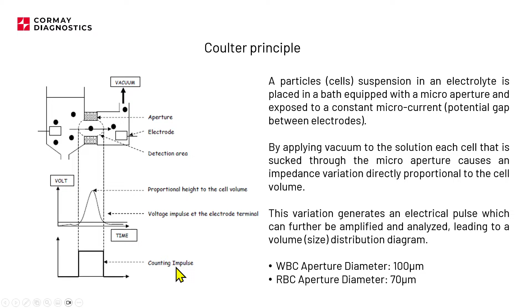This is the exact diagram of the Mythic 3CRP. In terms of principle, the Mythic 18 uses the same principle of measurement, but it's built in a slightly different way. But as I said, the principle is identical for the Mythic 18 and 3CRP. They call it the front tank electrode. The front tank is basically the chamber where the dilution happens, where the analyzer is making the dilution.